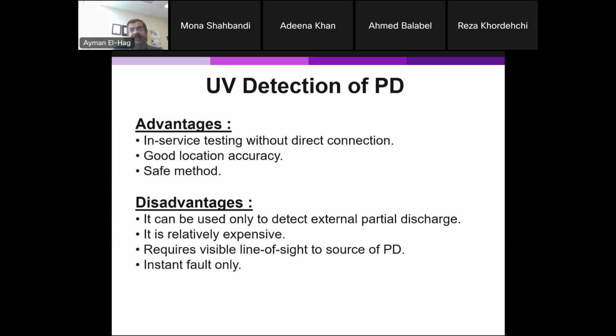And you can only see it if there is a fault happening right now. This is the same as the RF antenna, or the CT. All these techniques require the fault to be happening right now to be able to detect it. The only way you can detect the fault after it happens, if you are not physically there, is through the DGA, the dissolved gas analysis. Hydrogen is an indication of partial discharge inside the transformer. So if you take the sample after a few days, H2 is still there, so you know that at some time there was some sort of partial discharge.